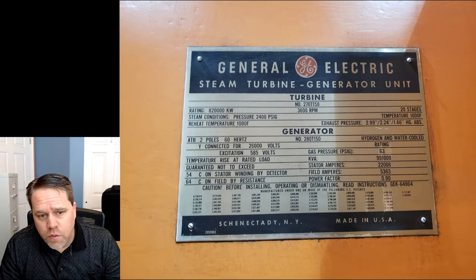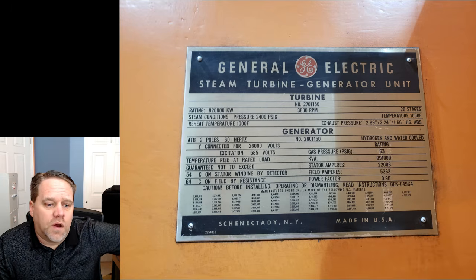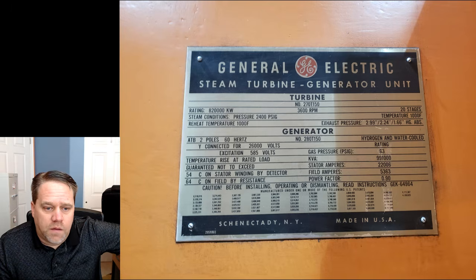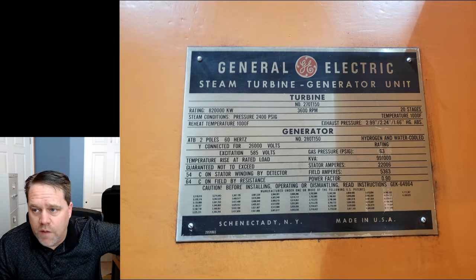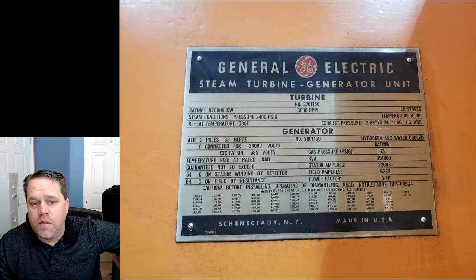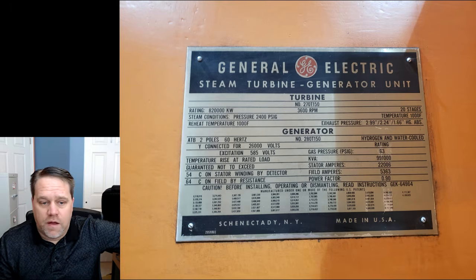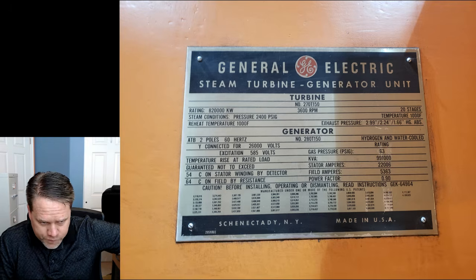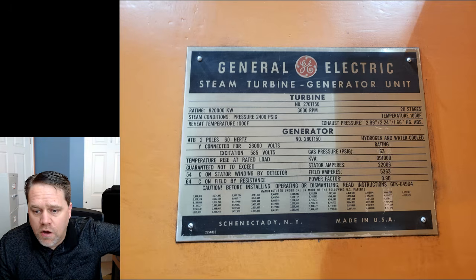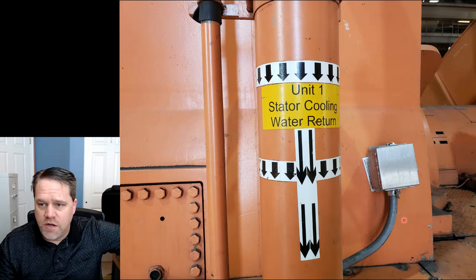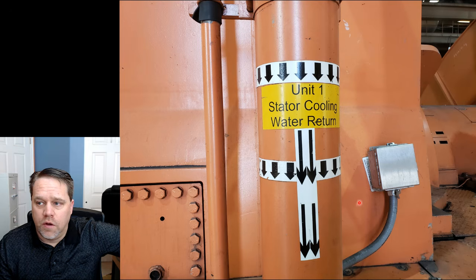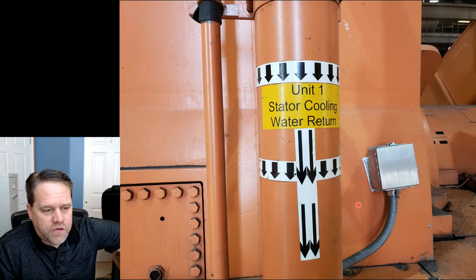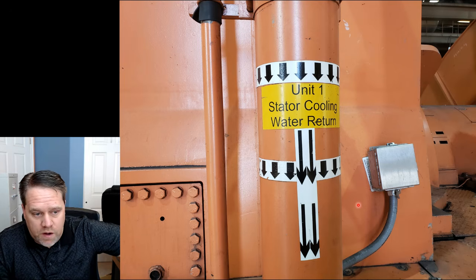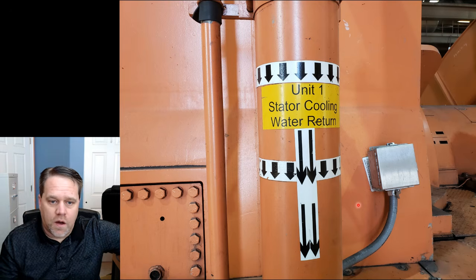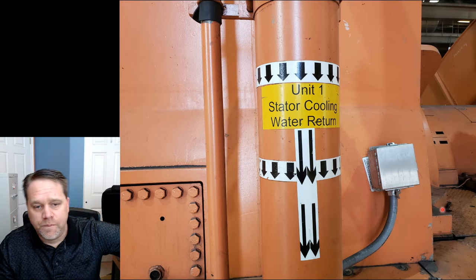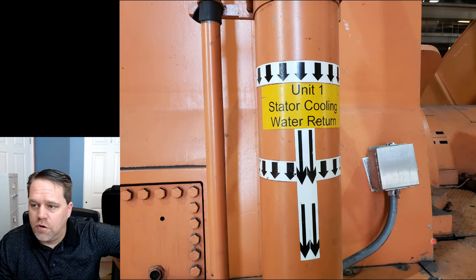So to determine the current, we would just take the 820,000 kW and divide it by 26,000 volts times square root of 3, and we come up with about 18,000 amps that come out of this generator. Of course, a generator like that runs rather hot, as you might imagine, so we've got cooled water that goes through it, and this is part of the role of the cooling towers that I mentioned earlier. So we've got to cool that water down so that it can cool down the generator, and there is the water return going through it.